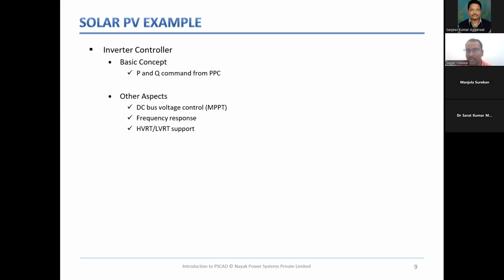100 milliseconds. But that's a problem, because LVRT, low voltage ride through, and high voltage ride through are very short-lived events. They can last for a very small time, for example a half cycle, quarter cycle, or one cycle. For a half cycle, the PPC may not have time to respond to this event. So for providing LVRT, HVRT support, the responsibility has to be given to something very fast, and that fast device is your inverter control.